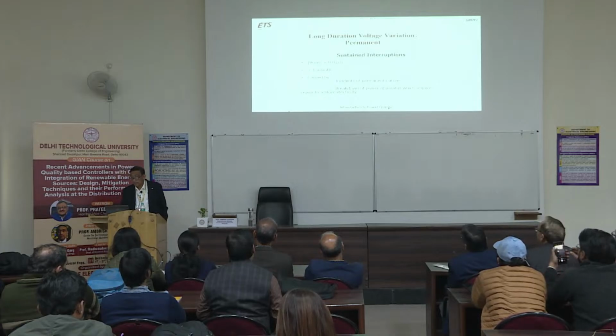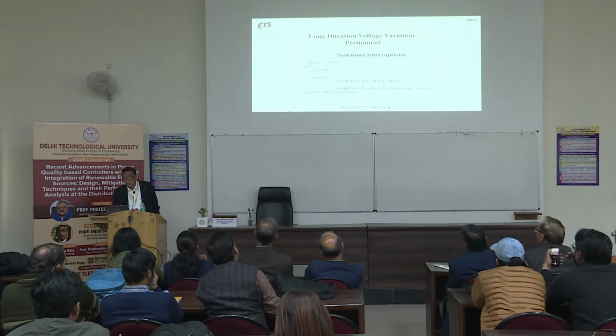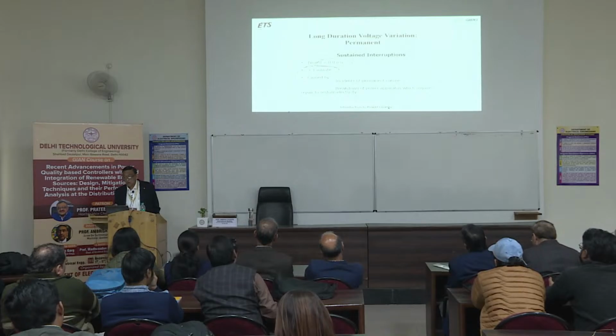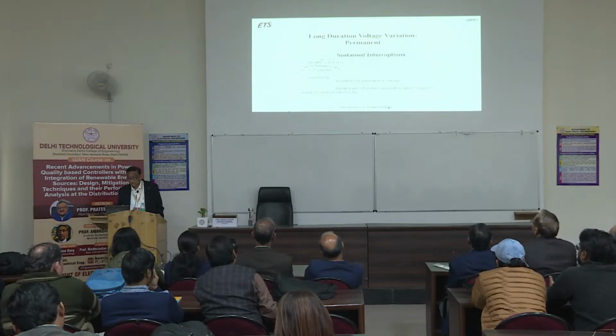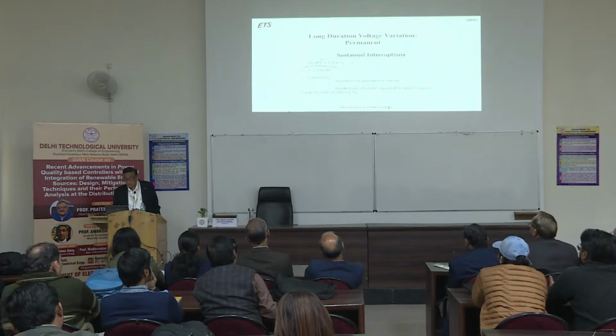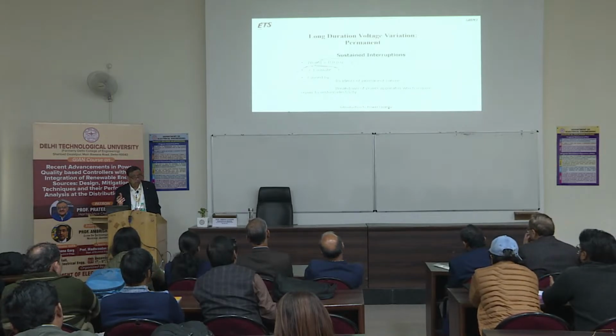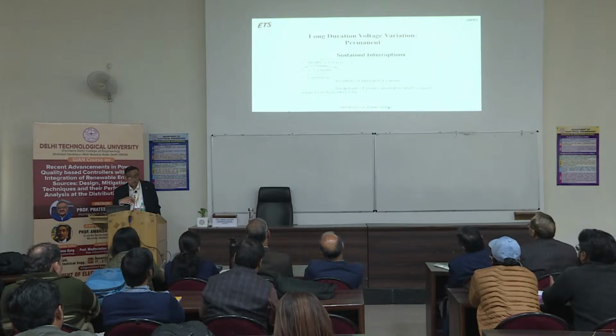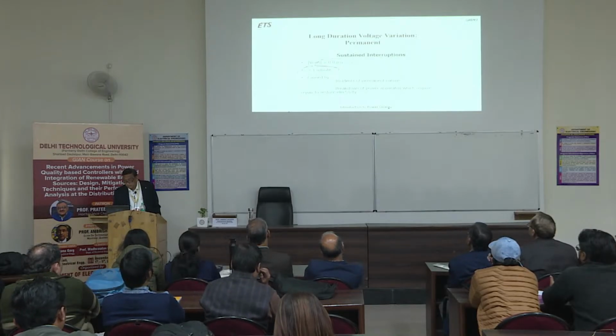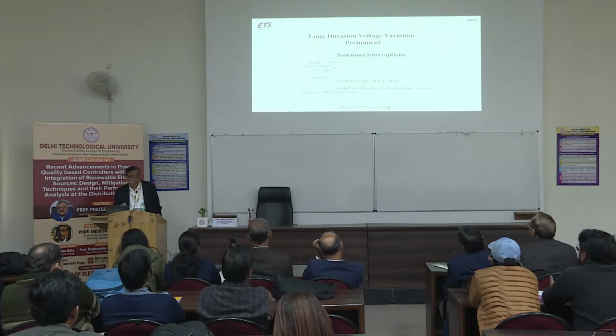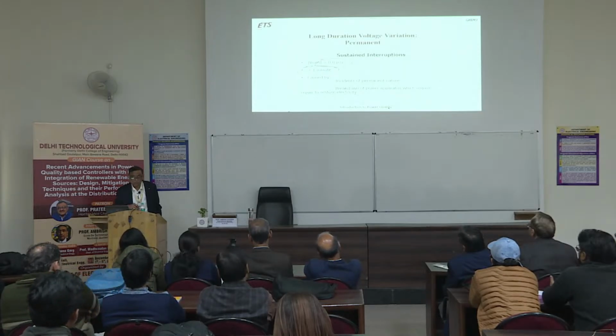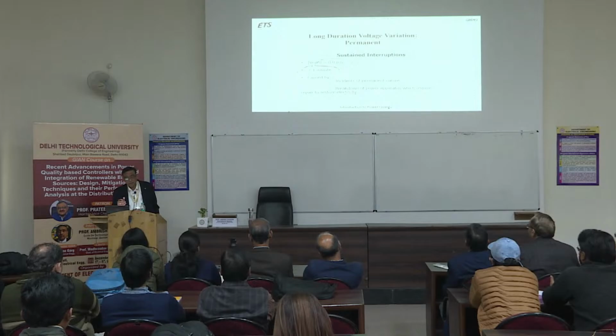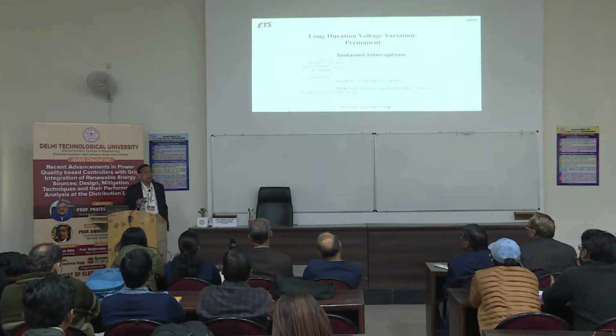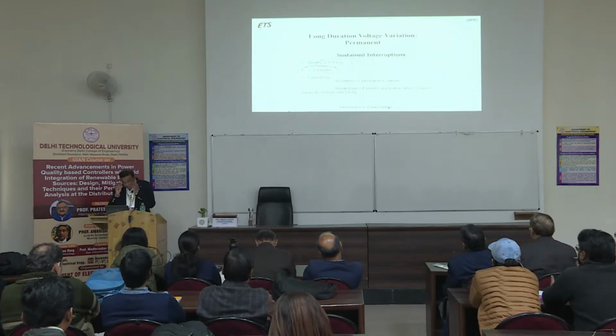Sustained interruptions: if it is more than 1 minute, your voltage is 0 pu. This is called a sustained interruption, caused by an incident of a permanent nature, like a storm came and a tree fell on the line, or a transformer burned out. It is a breakdown of power apparatus which requires repair to restore. Like if your transformer is burned out, now it has to be replaced or repaired. So sometimes in Montreal we have a Hydro-Québec truck that will come with a large transformer. Temporarily they will connect that transformer to replace this. This is what happens.